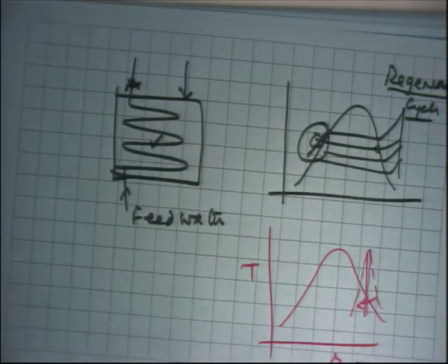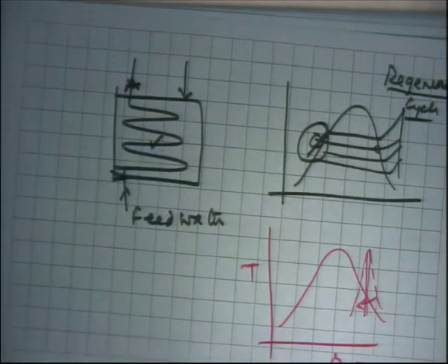So, every time the water goes through the deaerator, whatever dissolved gases in it are thrown out, so that the water is not corrosive anymore. Okay. Otherwise, the water can become corrosive. So, to make the water non-corrosive, you need a deaerator in the cycle. So, that is one of the feed water heaters where the steam and water are mixed, and the other feed water heaters are of this kind where the feed water flows inside the pipes and steam condenses outside the pipes.